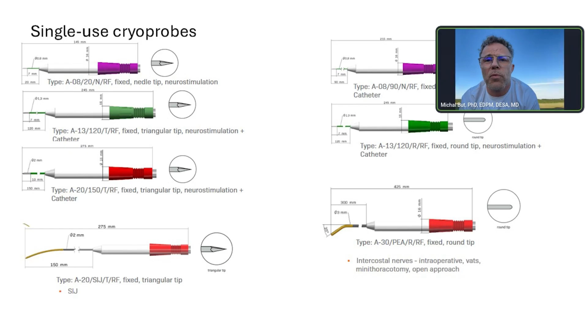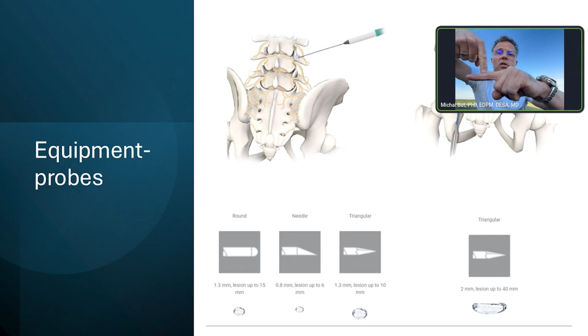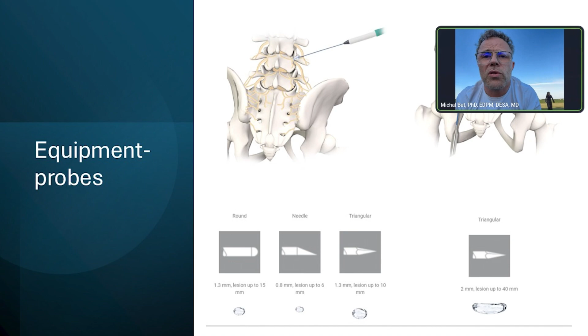The main difference is with the blunt probe. Is it possible to build some ice ball around the tip? If you have a sharp probe, the ice ball will end on the tip. If it's round, the ice ball will be a bit far from the tip. So if you want to target a nerve perpendicularly, it is better to use a blunt probe. If you can be parallel, use the sharp one, because you don't need to cut the skin or use the introducer with the sharp probe.